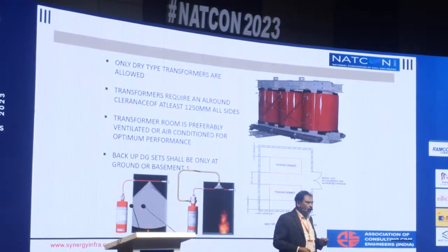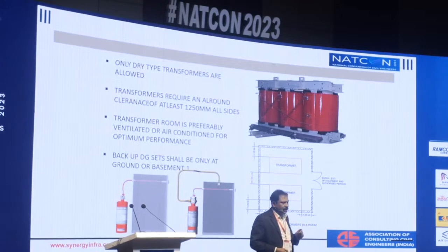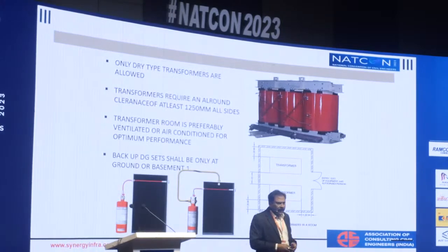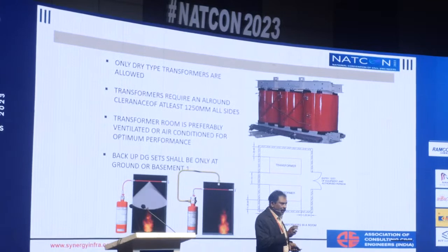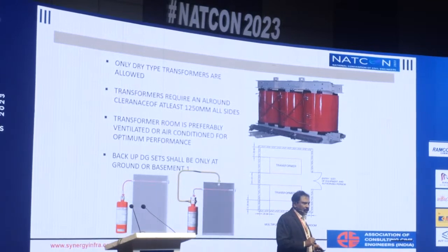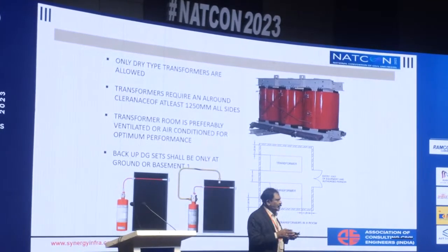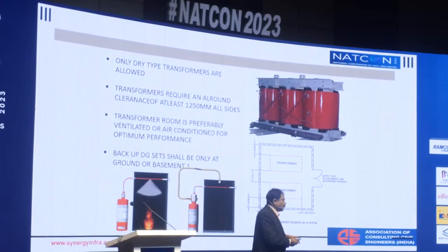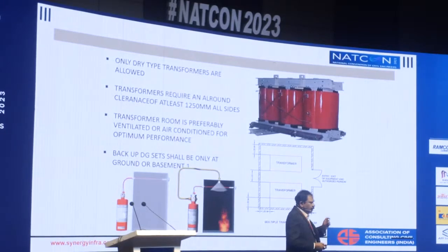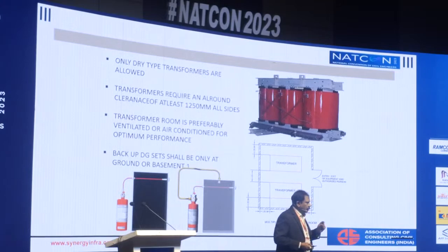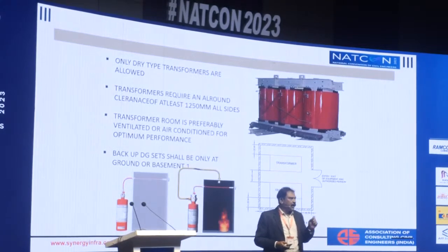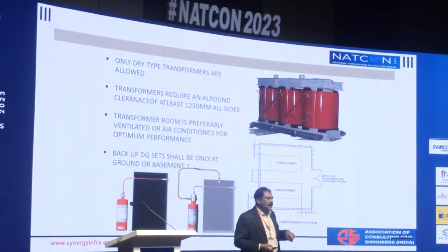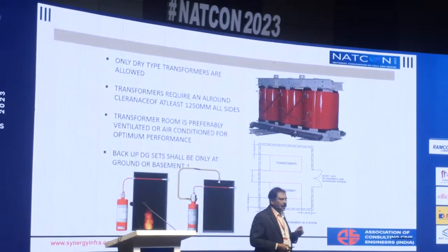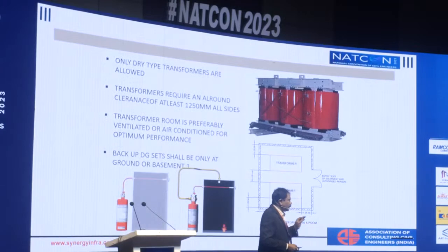And also, the recent National Electrical Code has introduced the arc flash detection device. Generally we might have heard about a leakage circuit breaker or a residual current circuit breaker. Whenever there is a leakage, 30 milliamps of current for a duration of 30 milliseconds probably cannot be fatal for any person. But anything beyond 30 milliamperes of current passing through a human body for beyond 30 milliseconds is going to be fatal, a person may die.